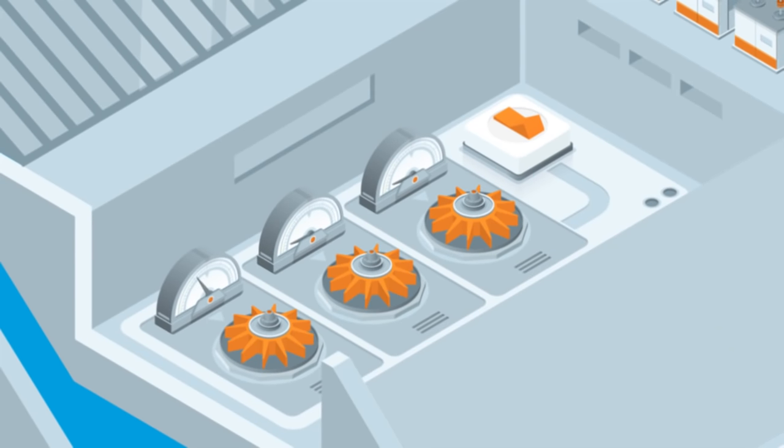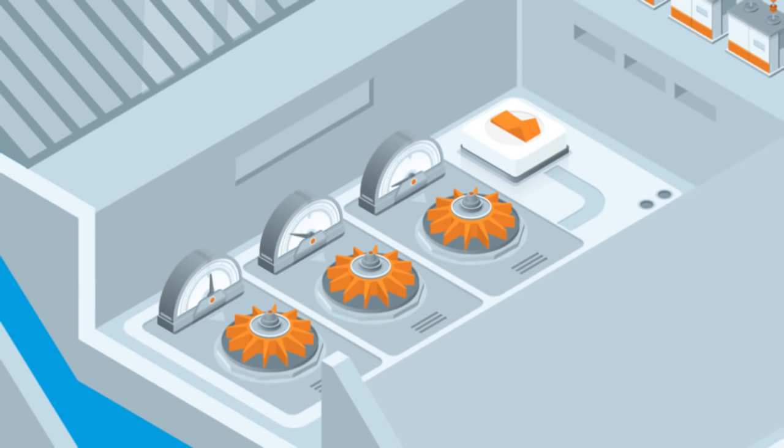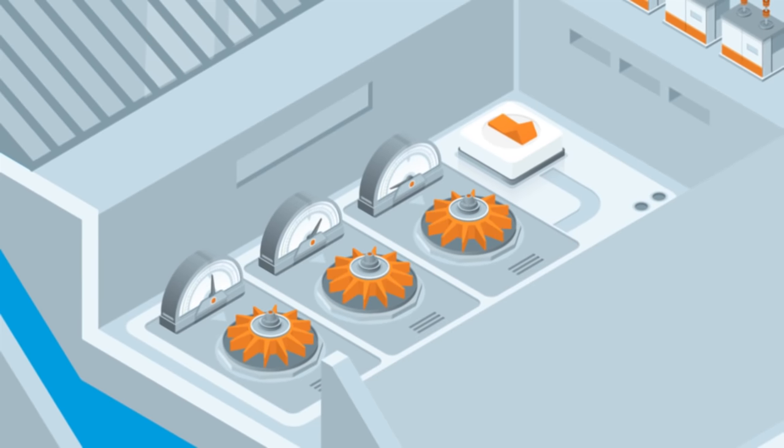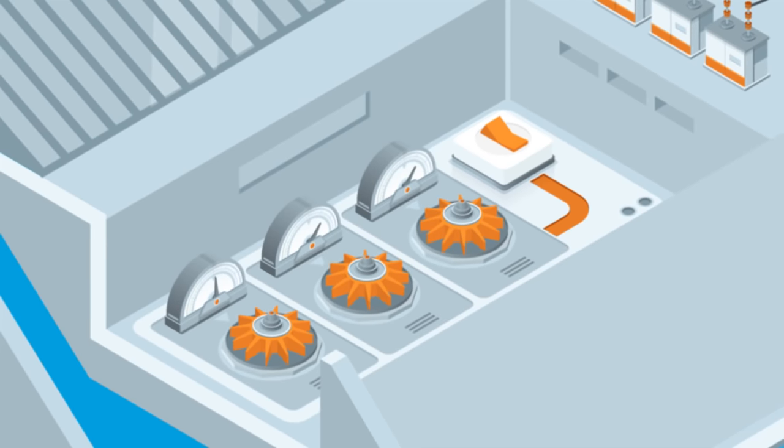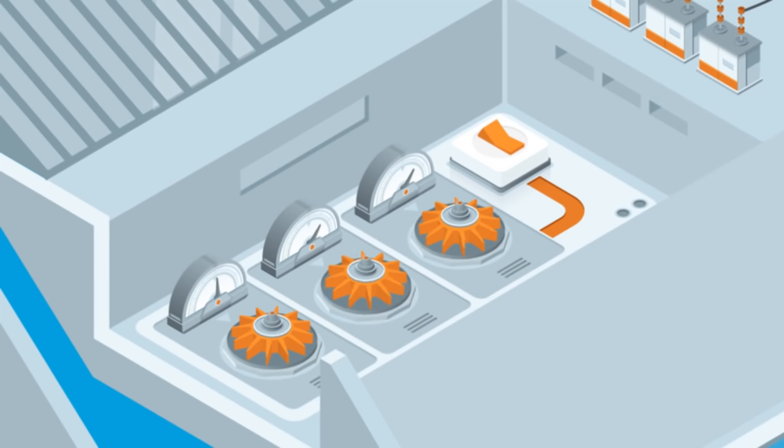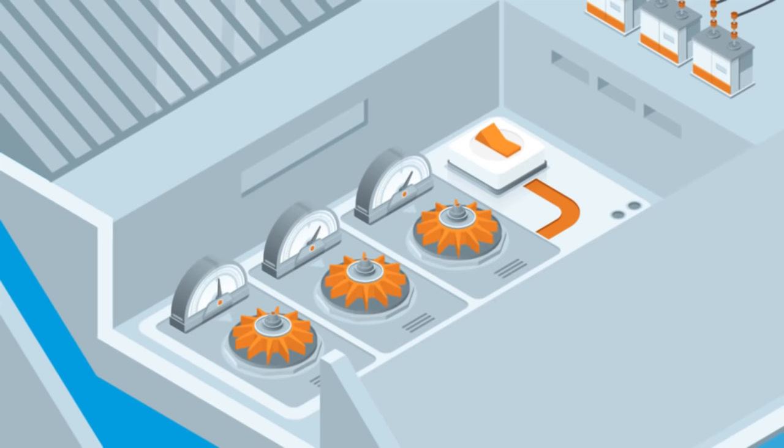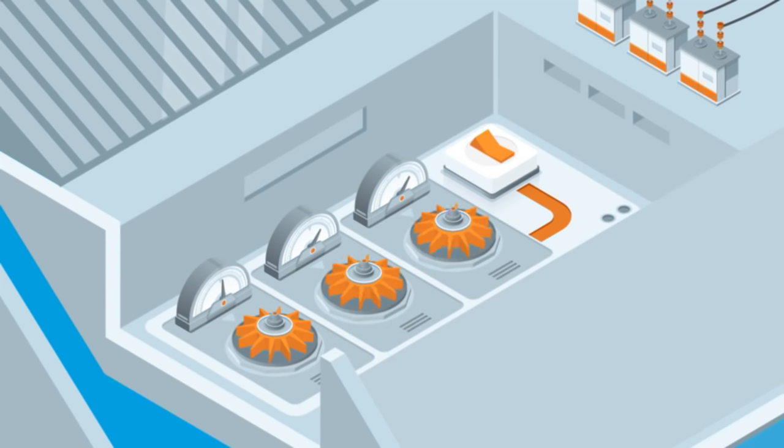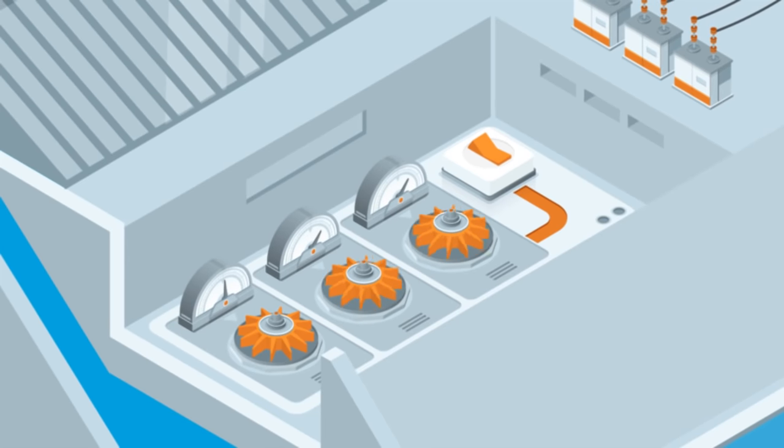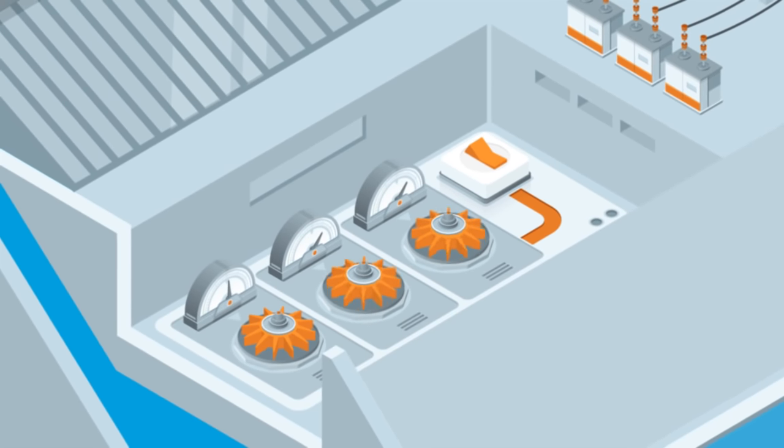Let's say that our plant, equipped for example with three 100 megawatt pumps, were to receive 270 megawatts of electricity in an off-peak period. If the pumps were fixed speed, they could only run at full capacity and only two of the three pumps would start. The upper reservoir would only be able to be recharged by 200 megawatts, and 70 megawatts would go to waste.